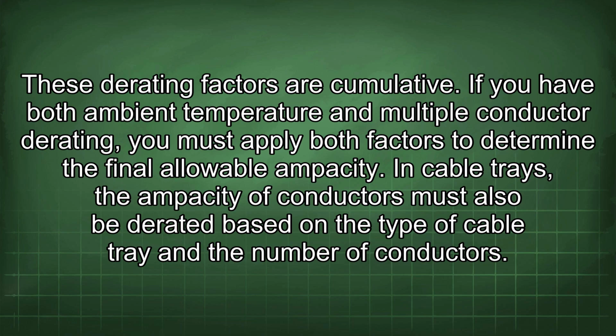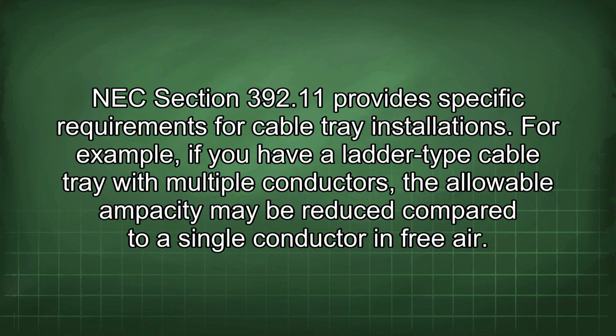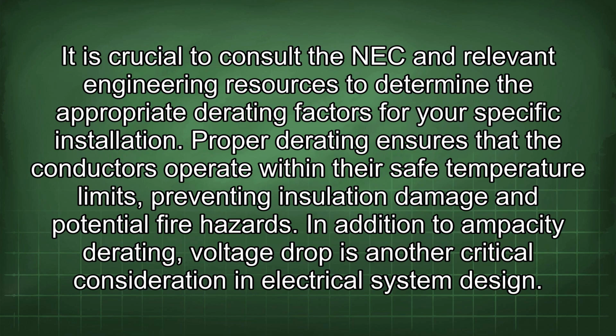If you have both ambient temperature and multiple conductor derating, you must apply both factors to determine the final allowable ampacity. In cable trays, the ampacity of conductors must also be derated based on the type of cable tray and the number of conductors. NEC Section 392.11 provides specific requirements for cable tray installations. For example, if you have a ladder-type cable tray with multiple conductors, the allowable ampacity may be reduced compared to a single conductor in free air. It is crucial to consult the NEC and relevant engineering resources to determine the appropriate derating factors for your specific installation.